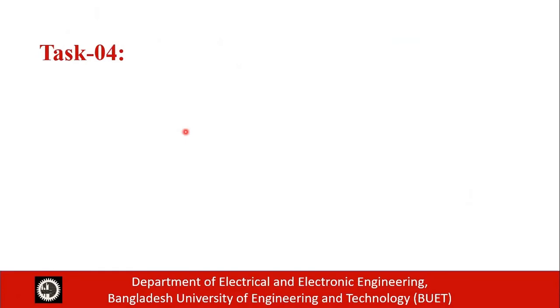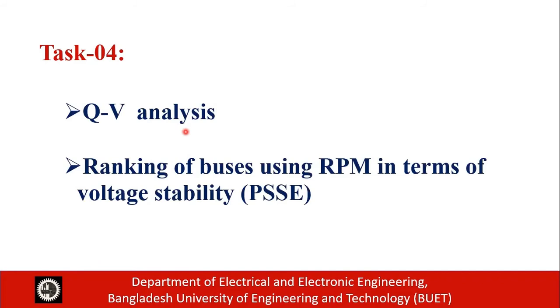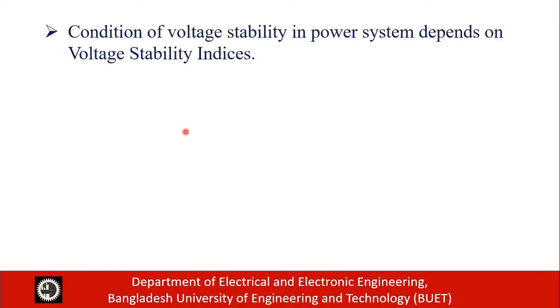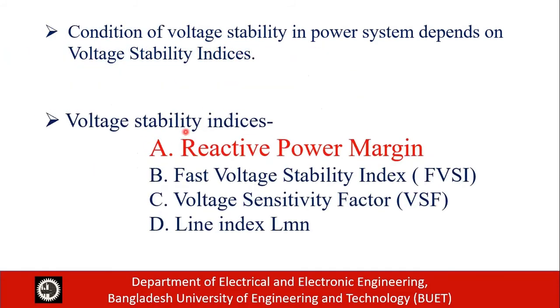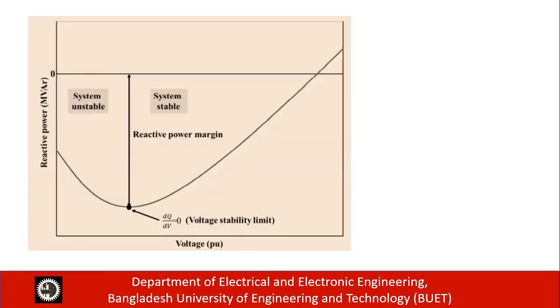Task 4 involves QV analysis and ranking of buses using Reactive Power Margin (RPM) in terms of voltage stability with PSSE software. Voltage stability in a power system typically depends on voltage stability indices; here we work with reactive power margin. This is our QV curve, constructed using the continuation method by increasing reactive power load while keeping the real power load constant. The bottom point of this curve specifies the stability limit or collapse point of the system. The base case operating point is shown, and the difference between that level and the collapse point indicates the reactive power margin.